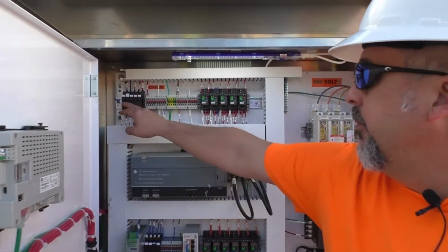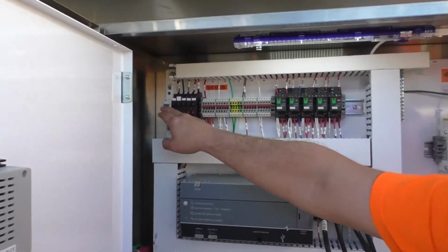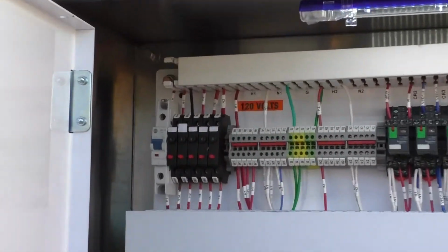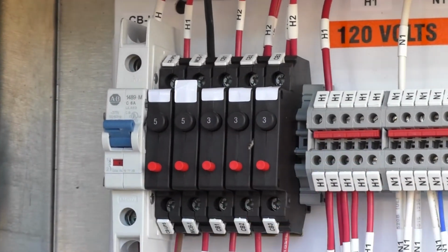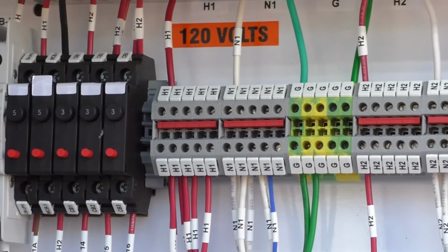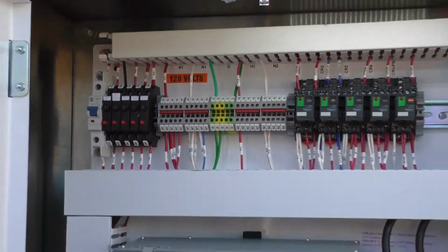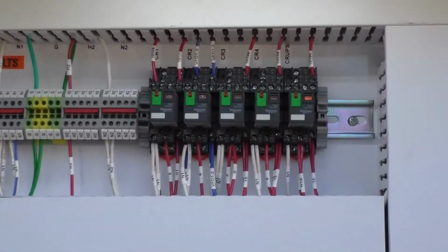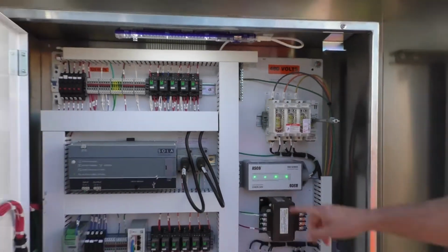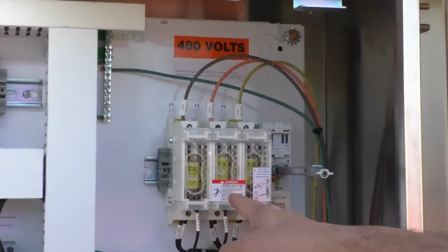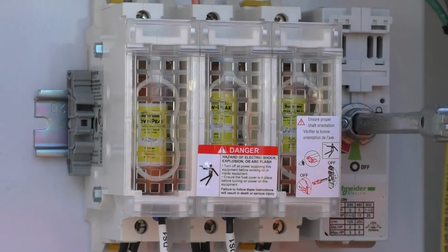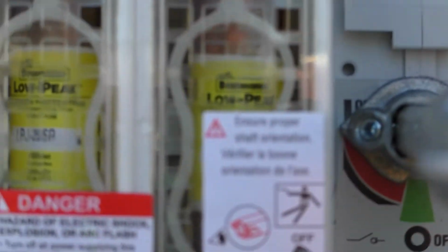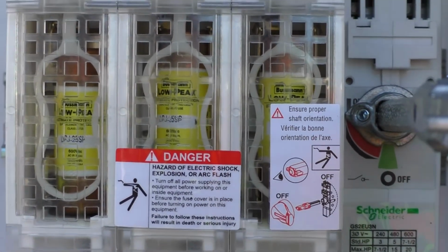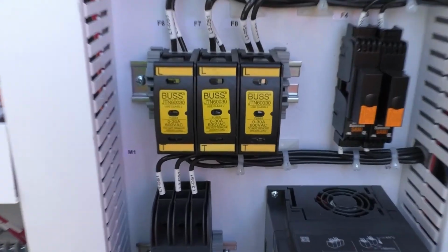So, battery backup. Here, these switches, this is your main switch to send power to your PLC. These are all related to the PLC and liquid level relay relays. If I had to recommend buying anything for spare parts, it would be these fuses right here. If you get a lightning storm and a surge of power comes through, these should be the first ones to blow. So I would buy them, and then I would buy some of these right here just as spares if I had to have any.